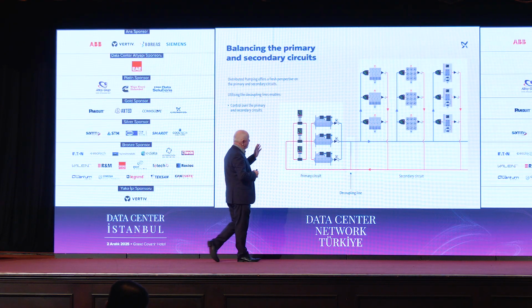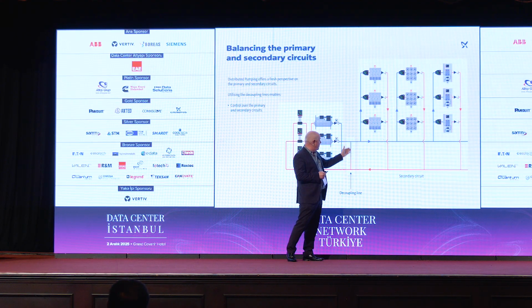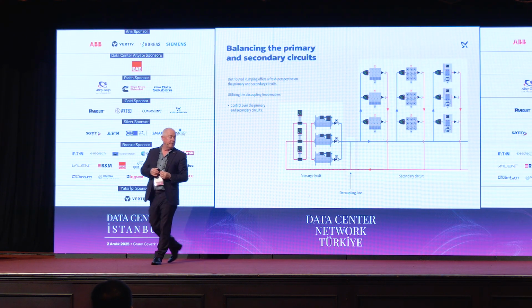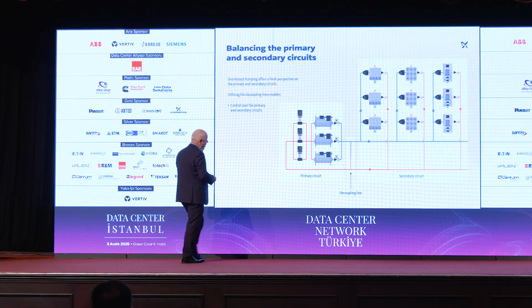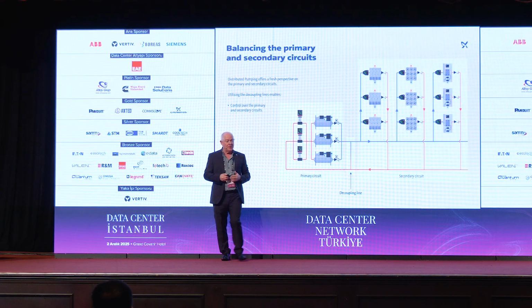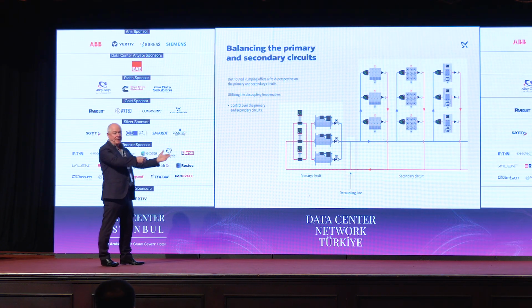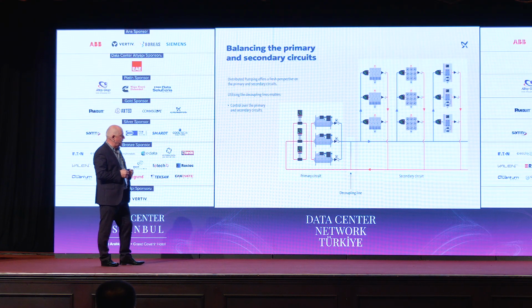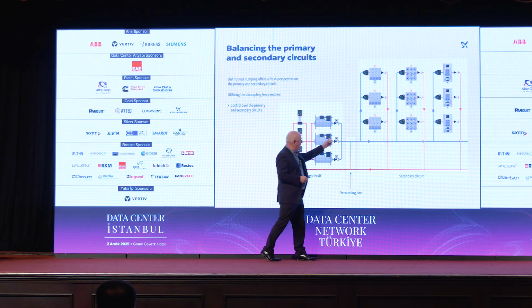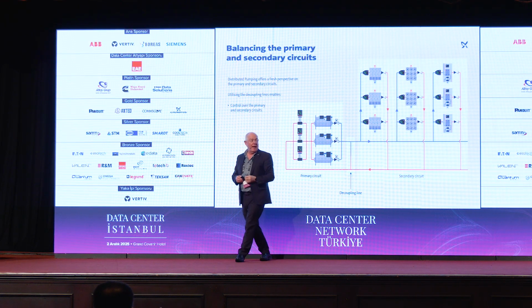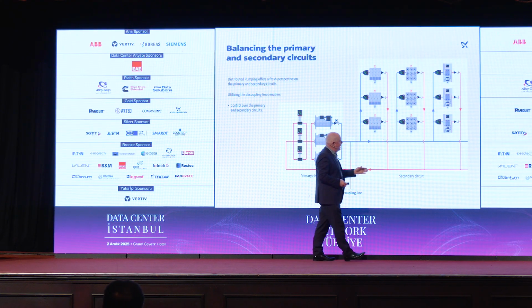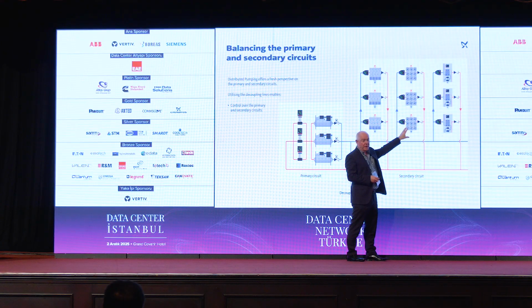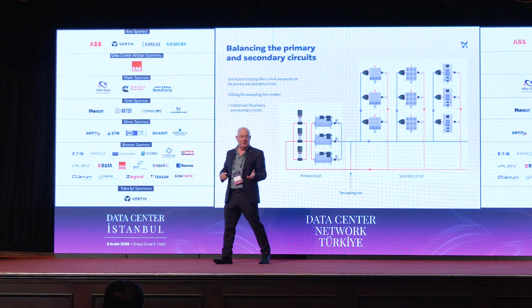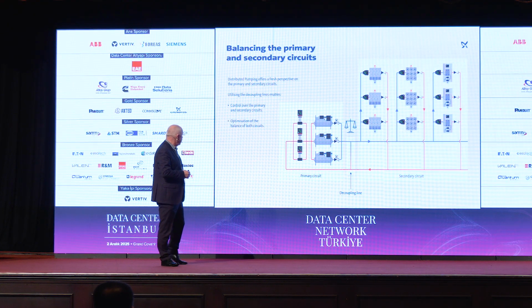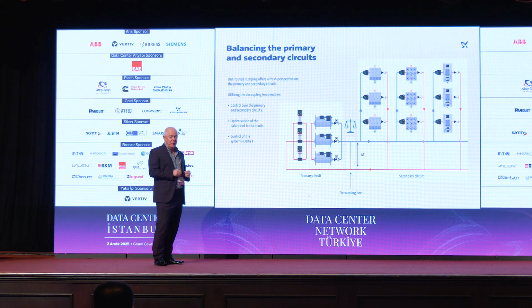So the ideal situation is we're generating chilled water, we're pumping it out to the secondary side, and we don't have flow in the decoupling line. And when we do this, the primary pumps will come down in size, so they won't be as big as the primary pumps you would see on a standard pumping system, because we've got our pumps out on the secondary side, which are taking up most of the friction losses. The primary pumps literally have to get it out to the decoupling line and back, and the other pumps will take the load from there on. If we have parts of the system shutting down, each pump will then take over and provide the load for its cooling load, regardless of what else is going on in the system. So it's autonomous really to its own load. And we optimize the balance between the primary and secondary sides. And as I mentioned, the delta T, and I'll show you in a moment how we manage that delta T.